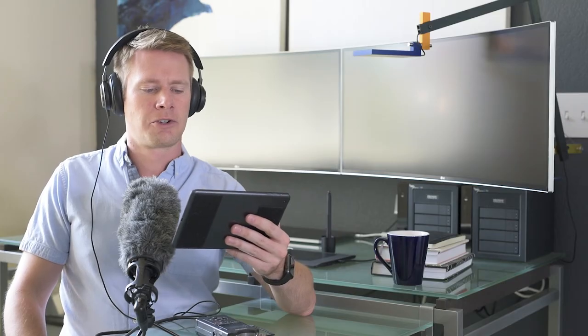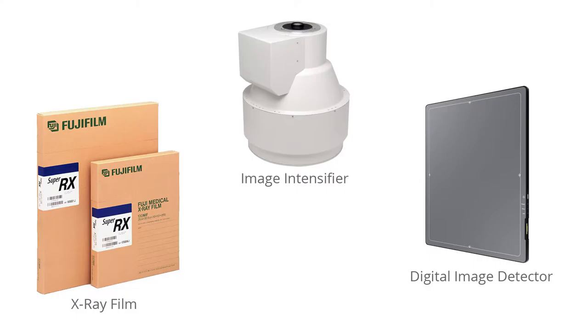The third type uses digital array detectors, which consist of thin film transistors that either indirectly detect light emitted from a scintillator material like cesium iodide, or directly capture the electrons produced when x-rays hit the detector.